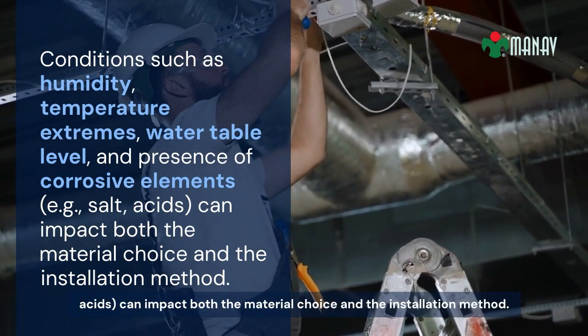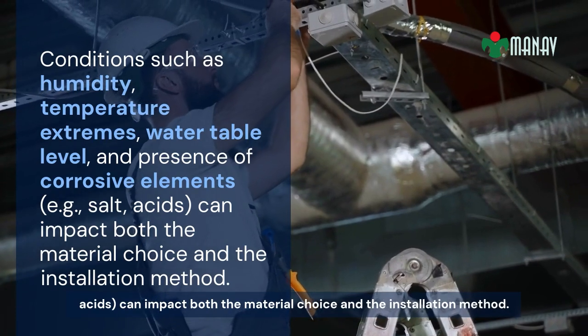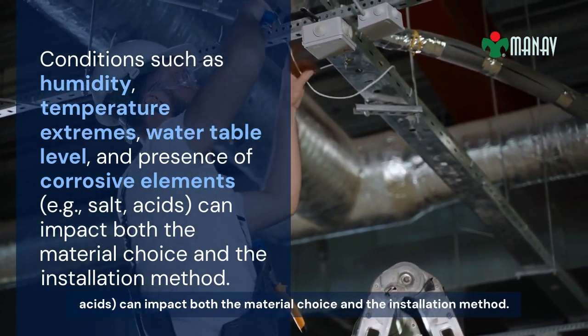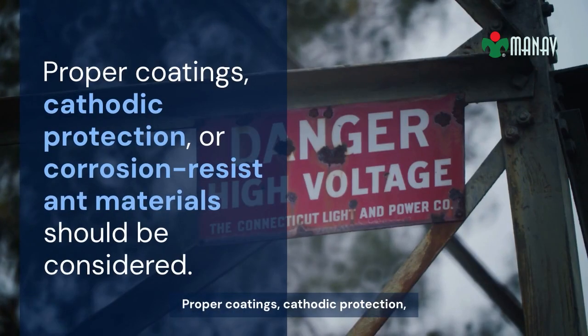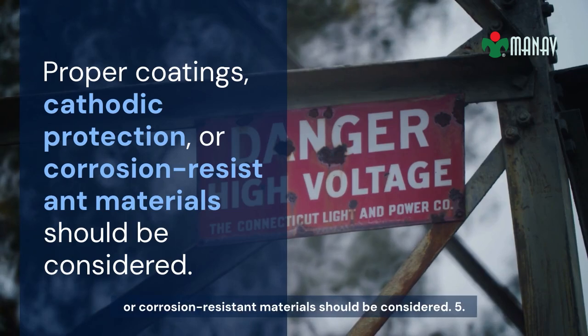4. Environmental factors. Conditions such as humidity, temperature extremes, water table level, and presence of corrosive elements, e.g., salt, acids, can impact both the material choice and the installation method. Proper coatings, cathodic protection, or corrosion-resistant materials should be considered.